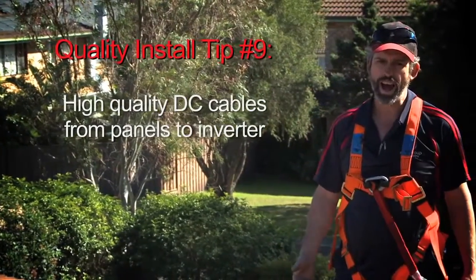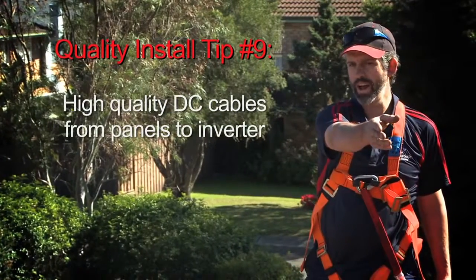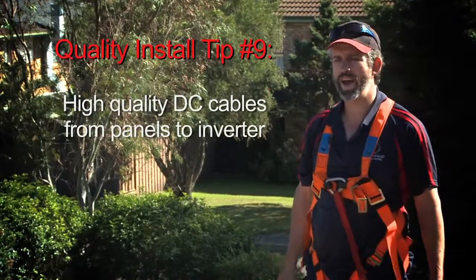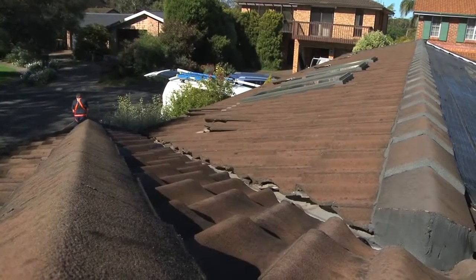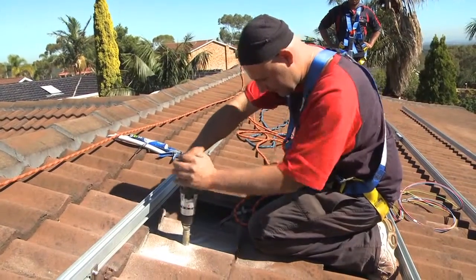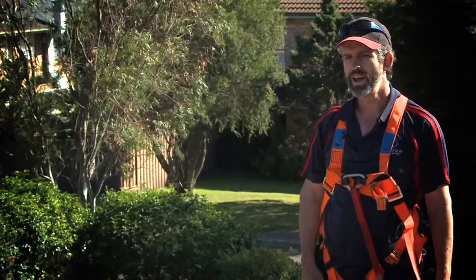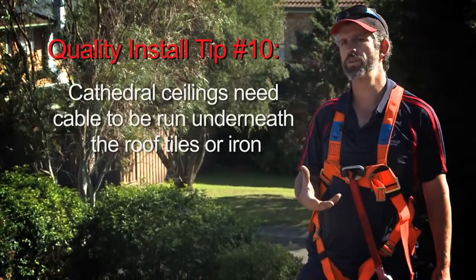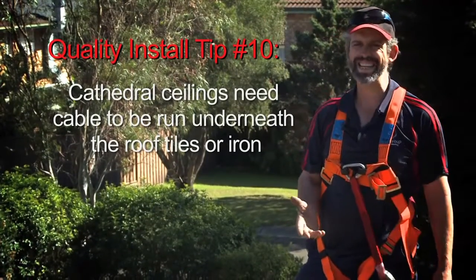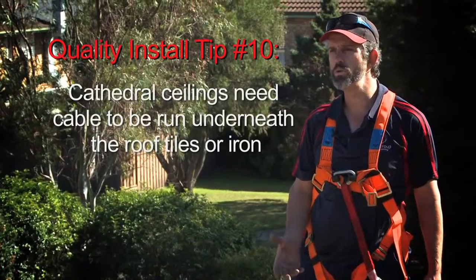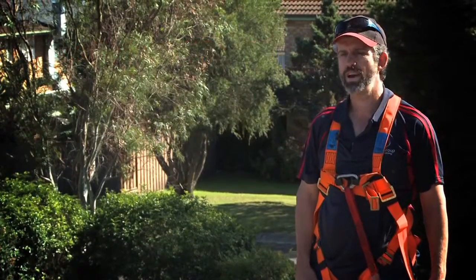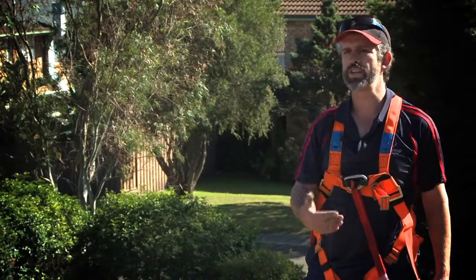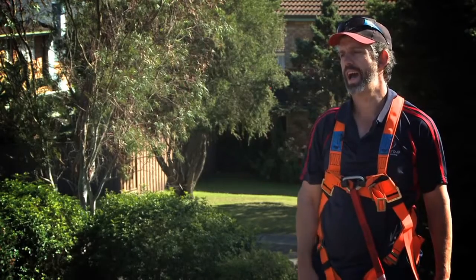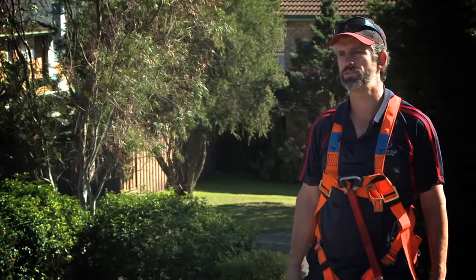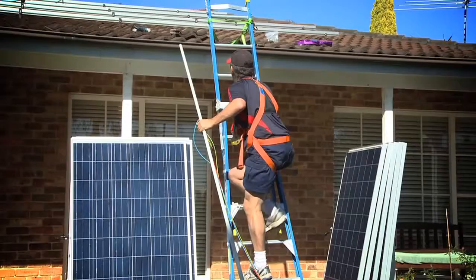Just up in the top left-hand corner, I've moved a tile out of the way, and after discussing with the rest of the team, this is where we're going to do a penetration for my cables to come out. The reason I've picked that spot, it's higher in the roof, so if I've got to get inside the roof, I've possibly got more room in there to move around in, plus it's making it a shorter distance for our cable, which we try to keep as short as we possibly can.